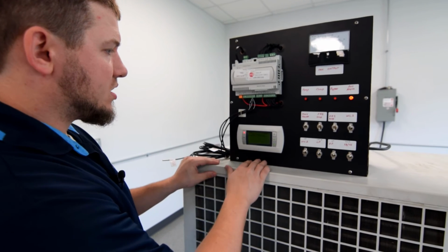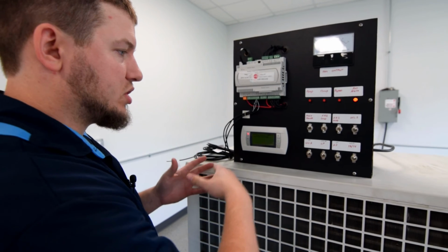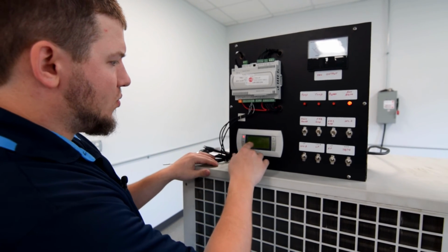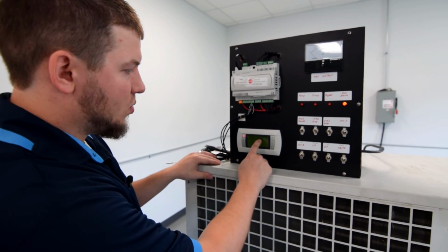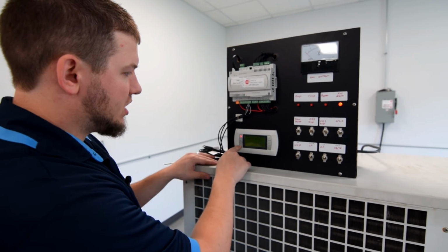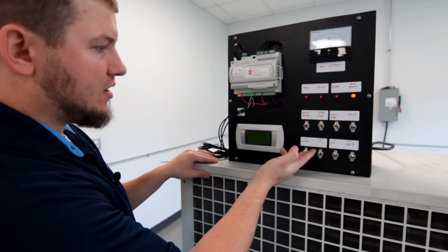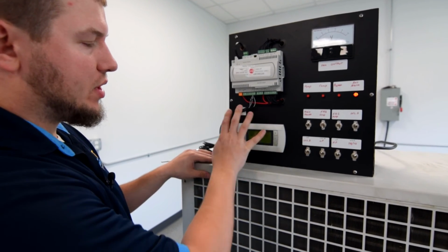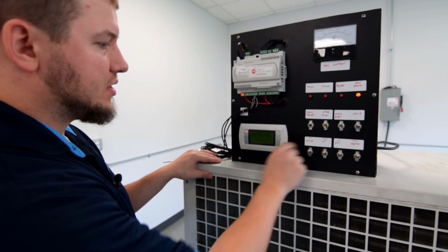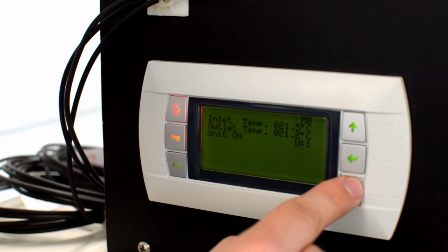So once you get to the site and you determine that you want to bypass this and you actually want to watch this high pressure situation happen, you're going to want to make sure you know exactly what the issue is and document that. Obviously this is a high pressure, so we're going to hit the escape button. I had turned it back off so we've resolved the issue and we want to remove this out of the situation. So the high pressure switch has been resolved. What we're going to do is go to page M2.